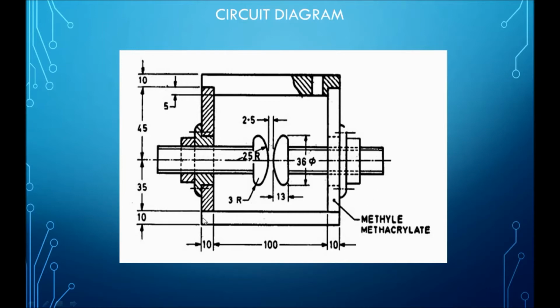I have tested the insulation strength of the transformer oil according to the Indian standard IS 335, following the standard IS 6792. This is the standard oil testing kit. You can see the diameter is specified here, 36, and the curve is 25 R, and this is the standard, and distance you can set 2.5 according to the Indian standard. Already all the specifications are mentioned here.